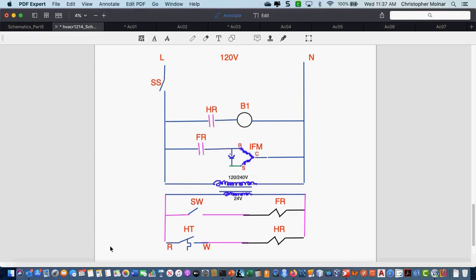Now, in oil burners, we have two types of motors that are primarily being used these days. The newer motors are all PSC motors. Okay, you're going to have a run capacitor on them. Some of the older motors are capacitor start, induction run. Again, let me repeat that. The newer burner motors are all PSC motors, and that's what I'm going to work with right now. I'm not going to get into the capacitor start, induction run right now.